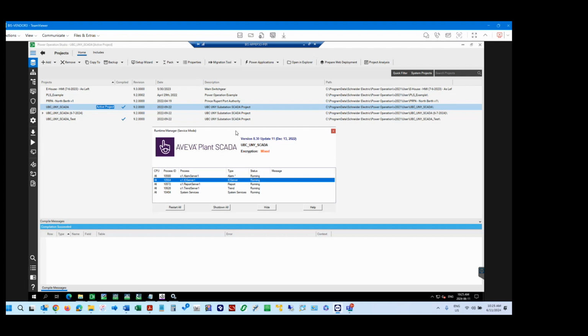Like, let's say you're having an issue with getting status from one relay, but the meter is operational, then you know that in that feeder there's something off with the relay's comms.